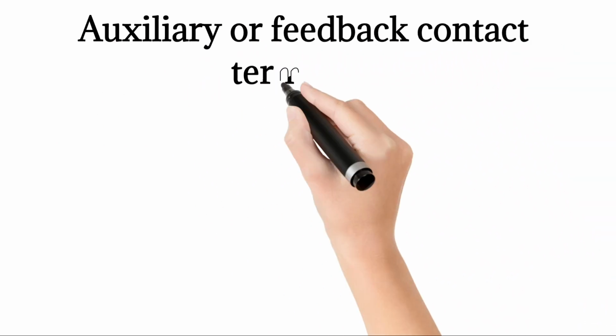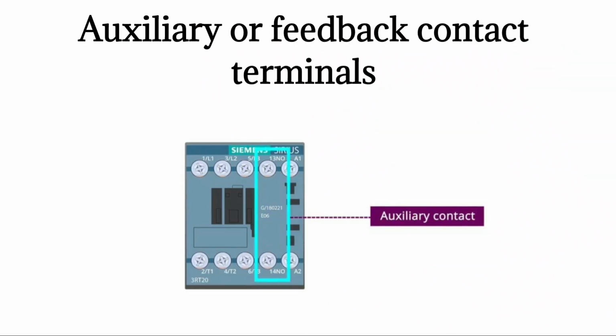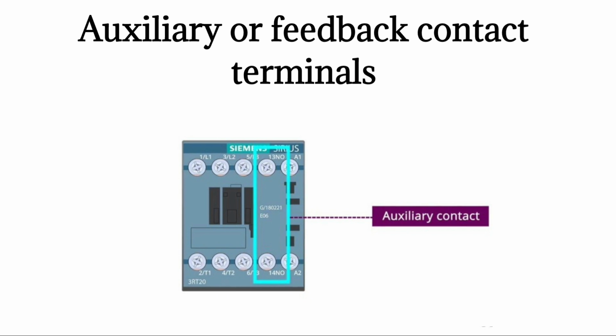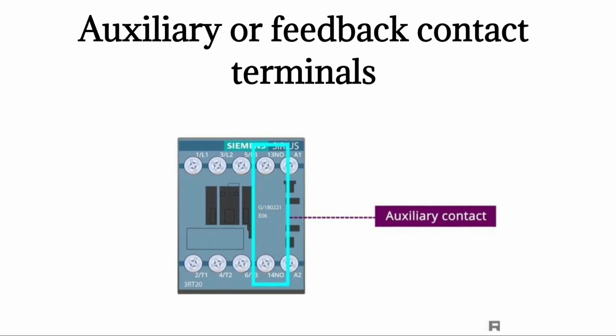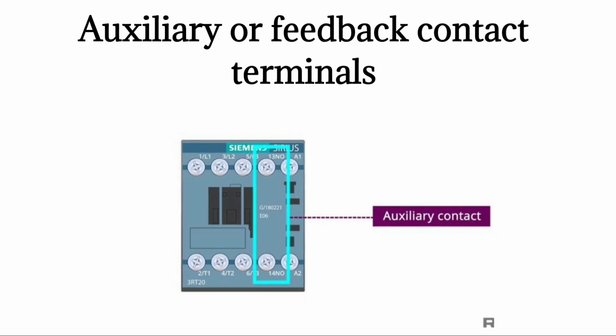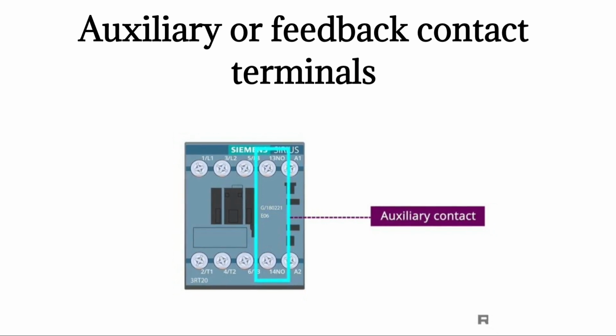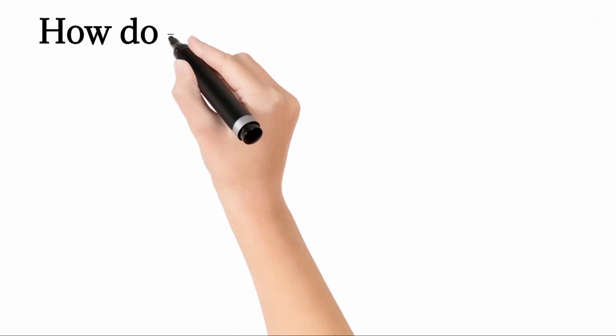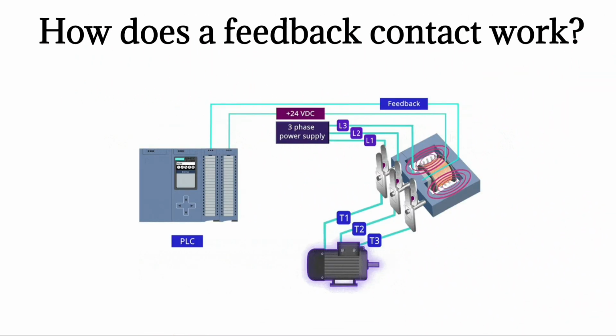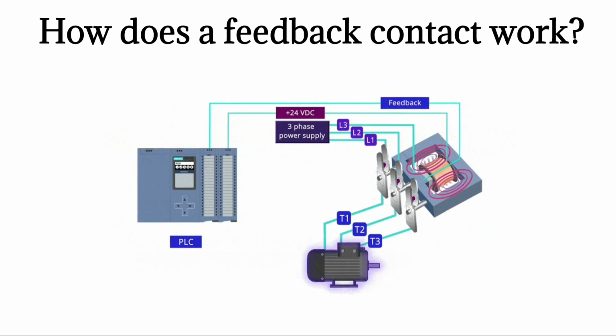Auxiliary or feedback contact terminals. As you can see, we have another set of wire terminals on the front end labeled as NO or normally open. This is a simple normally open contact referred to as an auxiliary contact or a feedback contact. This contact is used to send a signal to the PLC input about the contactor's health. What do we mean by that?